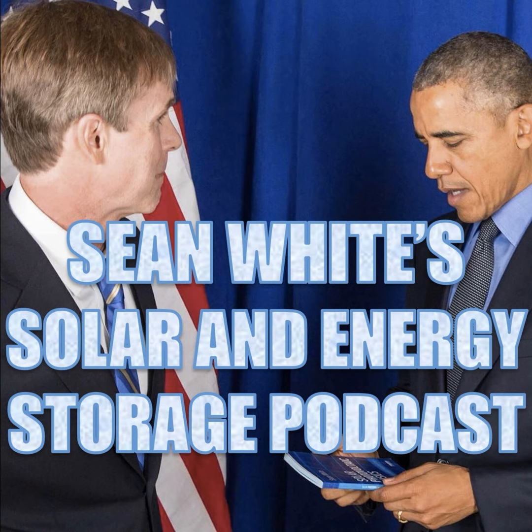Also, your equipment is going to be listed, and a lot of the listing will take care of this. So when you go buy what some people call a high voltage energy storage system, which is one that's not working around 48 volts most of the time, so we're going up over 100 volts at least, most people don't even consider that high voltage, but the people selling the energy storage systems are calling it high voltage when it's under 600 volts because there's lots of different definitions of high voltage. Utility people that work on the utility lines call 600 volts low voltage.